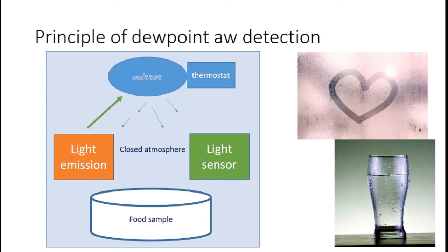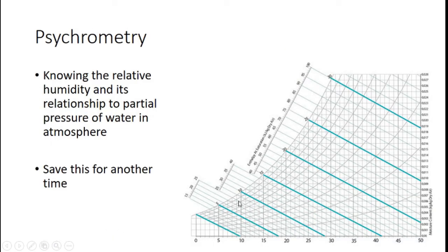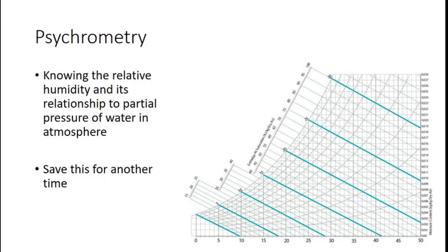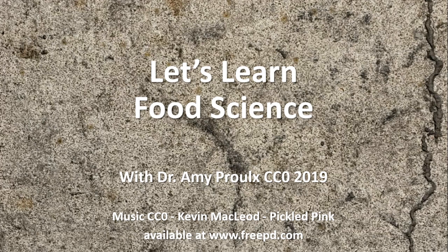You now know the water, or it will go through its own algorithm to identify what the water activity was based off of the relative humidity off of this sample. It is going through using a psychrometric table to be able to do that calculation. We will do a different presentation at a different time to talk about psychrometrics and relative humidity. But in general, going back to those water activity measures, it will give you out that number and that's all you need to do. You do not need to do any further analysis. You take that number and that will be recorded in your control document or it will be part of your product specification if you're doing product development. Short and simple. Take care and we'll talk to you soon.